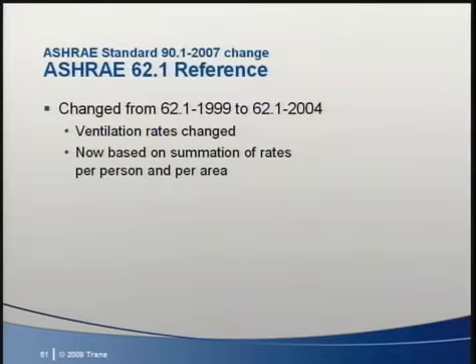While a fairly small change in the text of the standard, the reference to ASHRAE Standard 62.1, Ventilation for Acceptable Indoor Air Quality, changed from the 1999 version to the 2004 version. So addenda that changed Standard 62.1 are now used to define the minimum requirements of 90.1 also. As discussed on previous broadcasts, the addenda changed ventilation requirements, and for each zone the requirement is now based on the sum of a per person and per square foot requirement. Please refer to the Engineers Newsletter in the bibliography for more information.